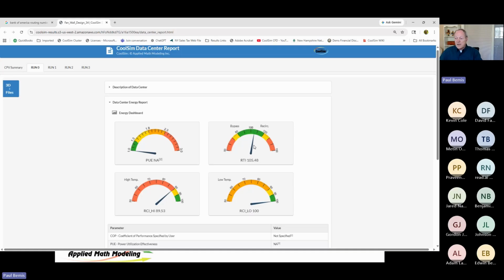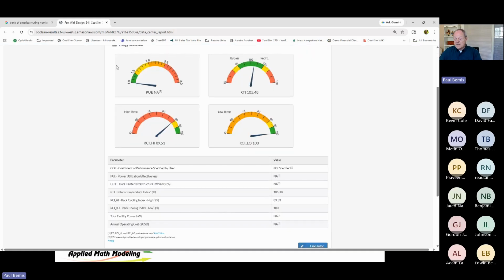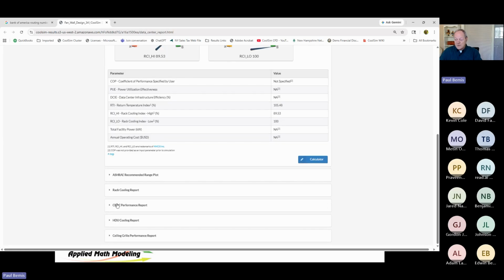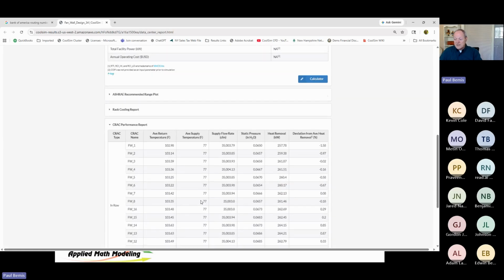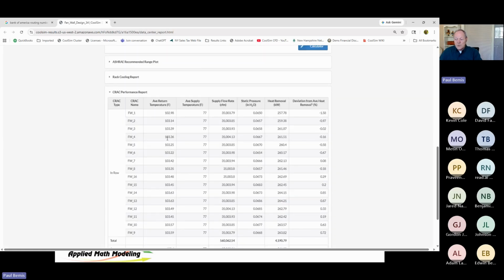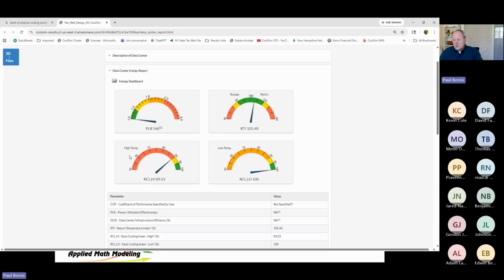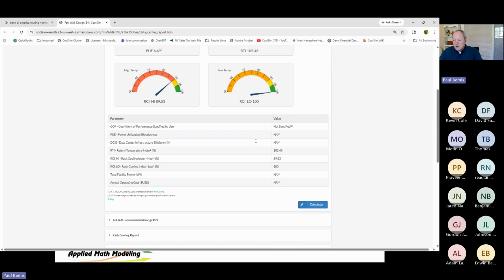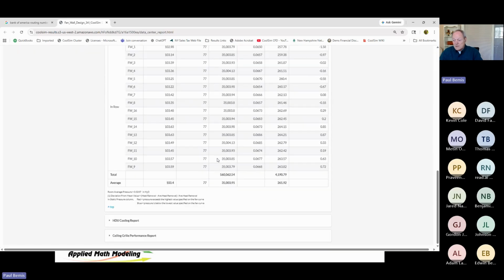So if we're running at a supply air temp here that's fairly high, let's take a look at our supply air temp down here under CRACs. We're supplying at 77. Our return air temp's 103. At 103 Fahrenheit, you start to run into issues with density. It will change. Remember, it changes with temperature. So it could be that I've got some trouble. I can tell just by looking at the numerics here that all is not great.